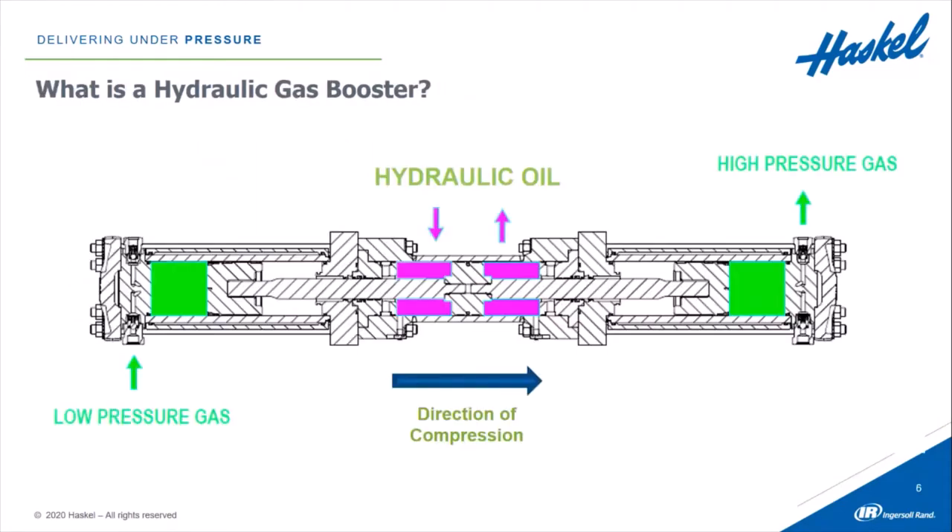This is an example of a Haskel hydraulically driven gas booster. The middle has a hydraulic drive. High-pressure hydraulic oil is pumped into the left side of the drive, causing the piston to shift to the right. The spent oil is pushed back into the reservoir of the hydraulic system. As that happens, it also pushes the piston into the gas section, compressing gas to as high as 15,000 PSI and out into the process downstream. On the left side, as the right piston moves right, the left piston draws in fresh gas from the source. When the system reverses, high-pressure oil pushes on the right side, shifting everything to the left, compressing gas on the left side and drawing in fresh gas on the right for the next compression cycle.